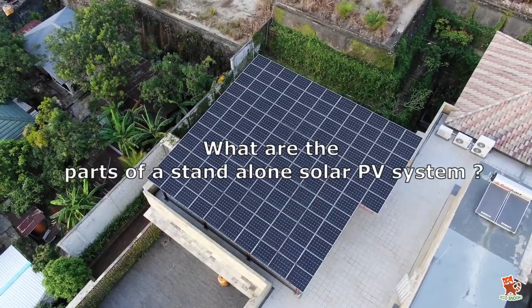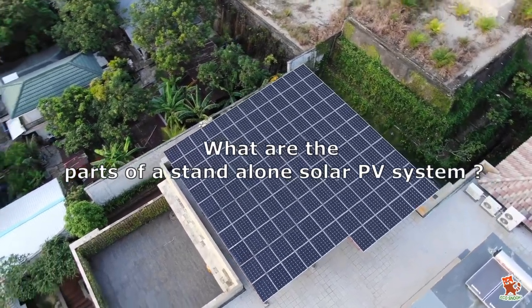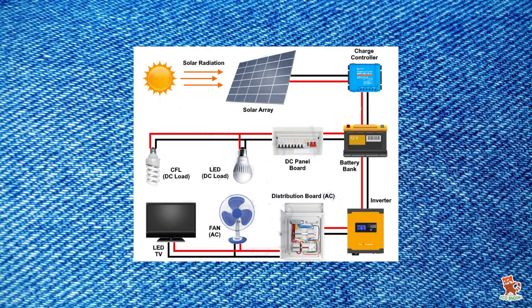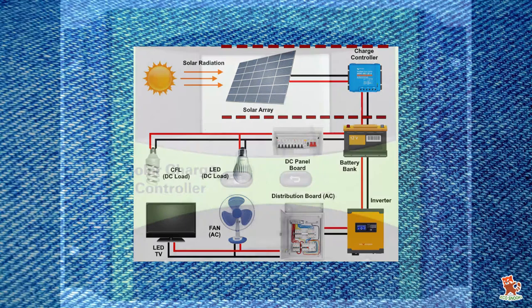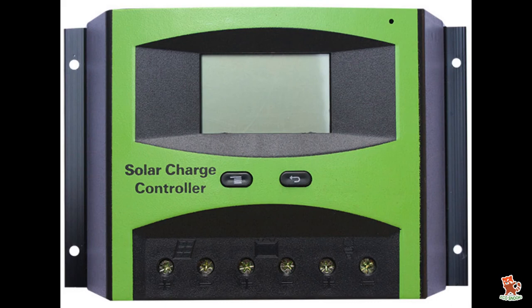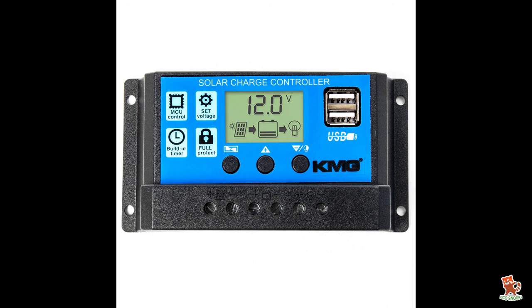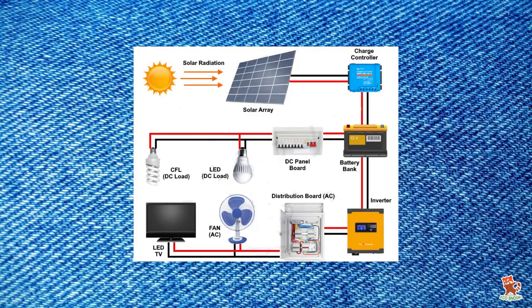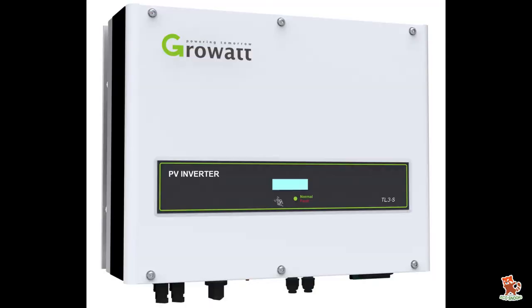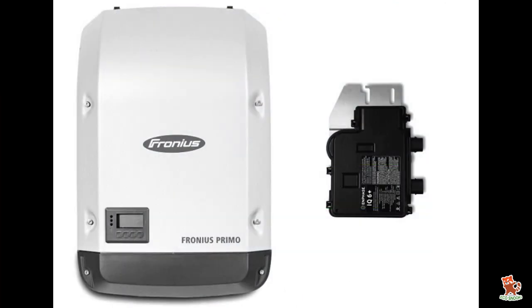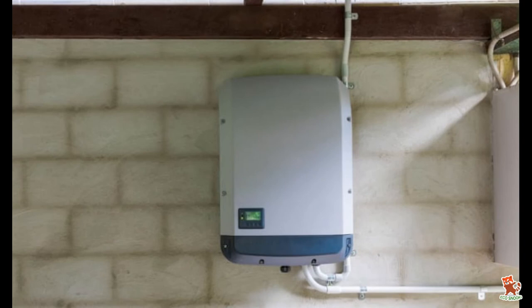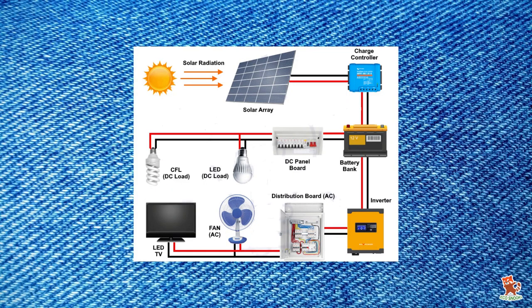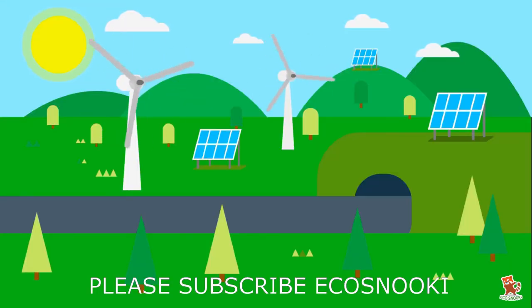What are the parts of an off-grid or standalone solar PV system? The solar panels absorb radiation and the electric current is given to the charge controller. A charge controller, or charge regulator, is basically a voltage and current regulator to keep batteries from overcharging — it regulates the voltage and current coming from the solar panels going to the battery. The batteries are connected between the charge controller and inverter. The basic function of an inverter is to convert the DC power that solar panels create to AC power usable in homes and businesses. If there is any DC load, an extra connection will be there between the battery and a DC panel board.